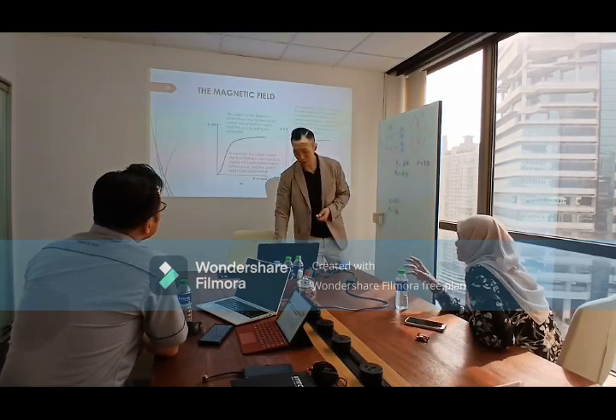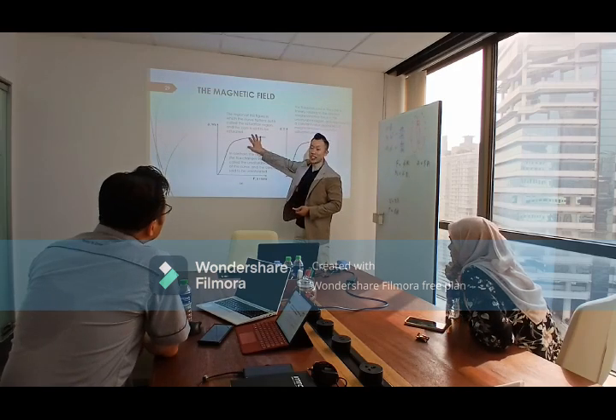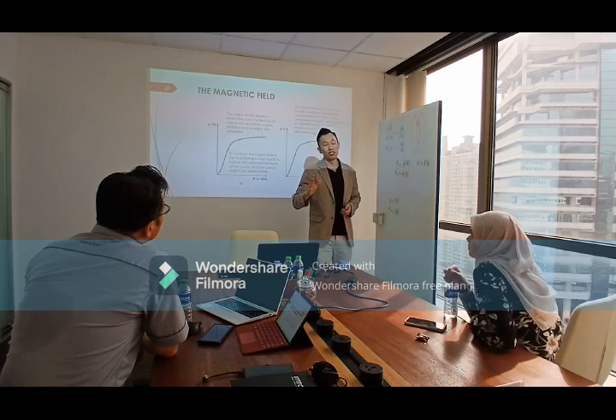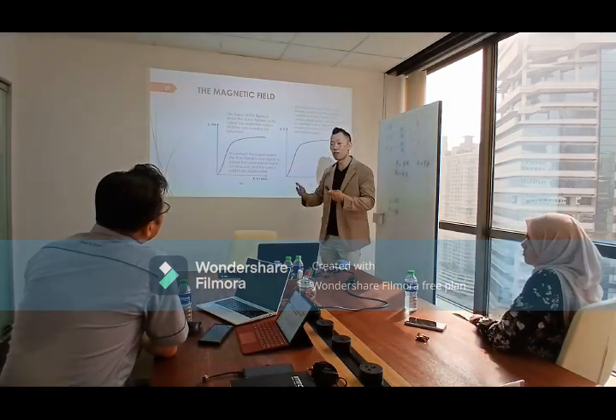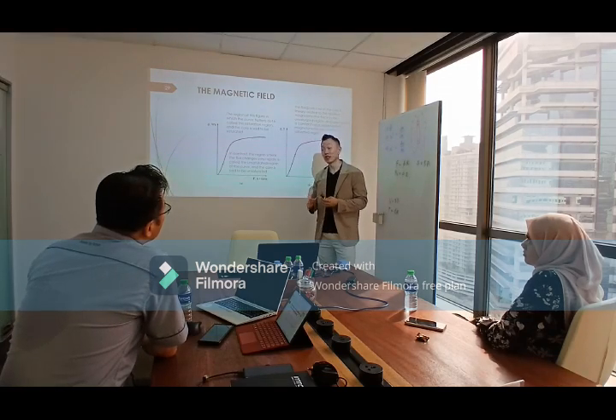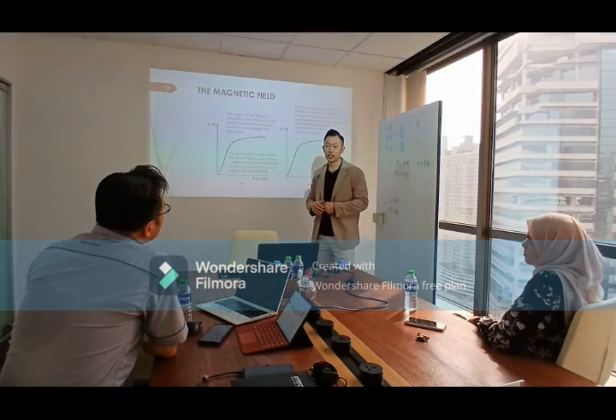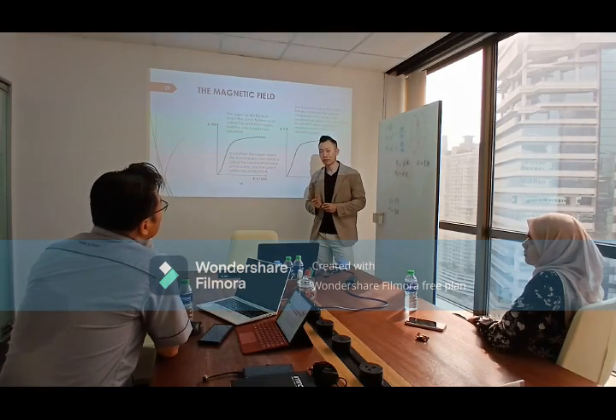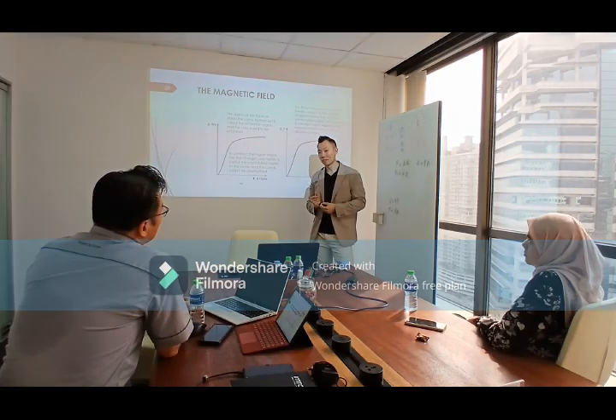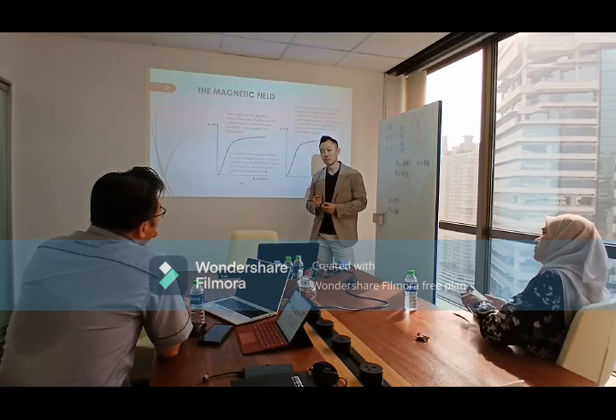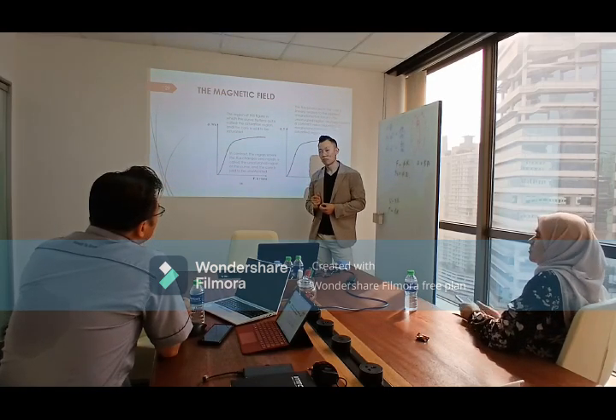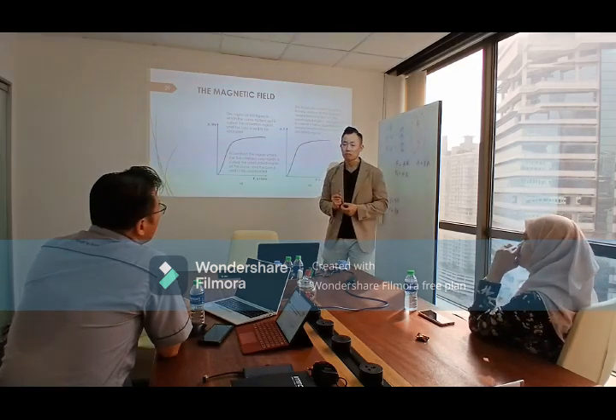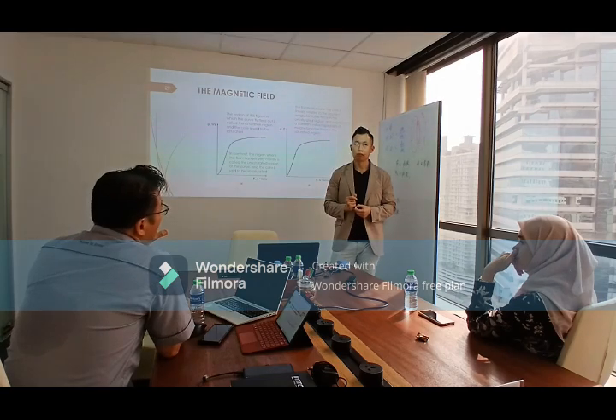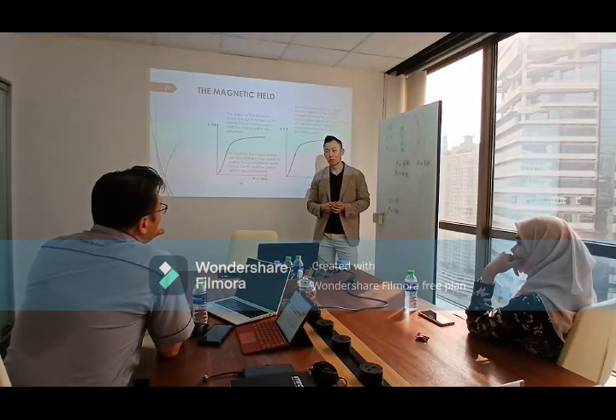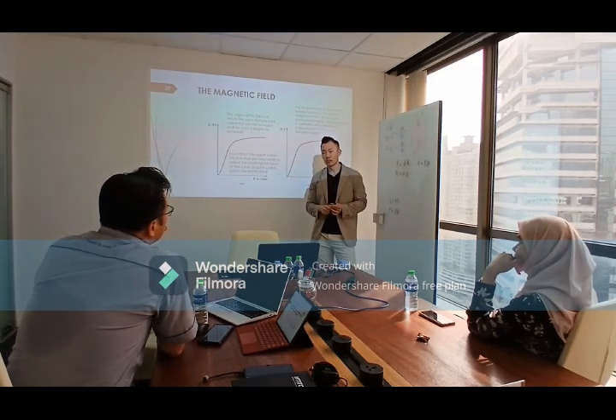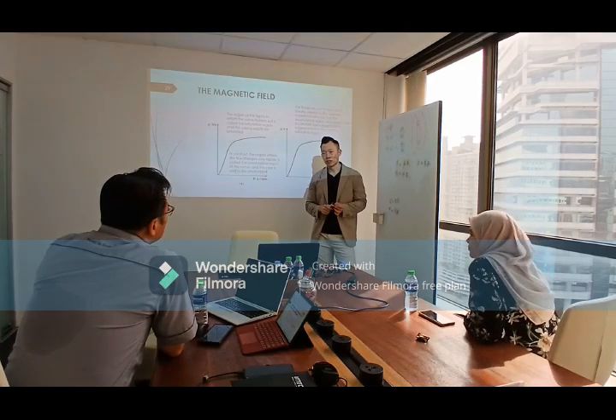It depends on the curve. If you are already operating in the saturation region, increasing current further won't have much effect on how fast the electric machine can turn. For a synchronous machine, speed is fixed at synchronous speed, say 3000 RPM, so it cannot turn faster even if current increases. Although flux increases, the power factor of the motor, rated originally at 0.85, may be affected, and the angle may be affected by this voltage loss, because the motor may consume more than it's supposed to.